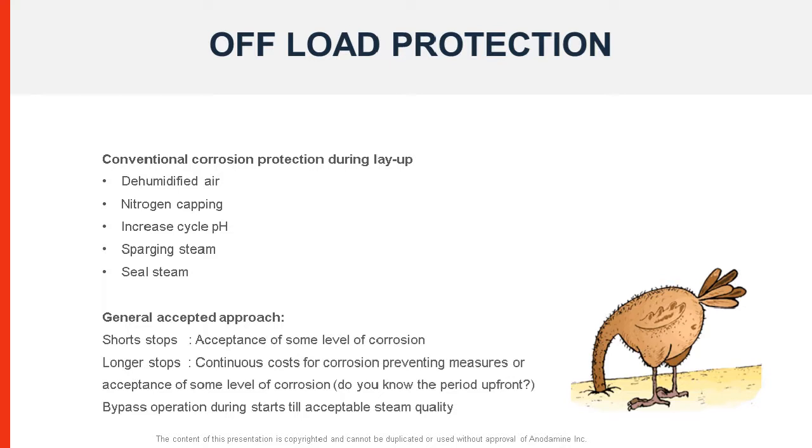Failure mechanisms will interfere with the plant's availability. It's that simple. The choice of cycle chemistry is strongly depending on the metallurgy and how the unit is operated. Extended offload periods leaving oxygenated stagnant water in any circuit is bad practice and will cause pitting and increased loads of oxide transport during starts. In most of the plants, operators increase the pH with extra ammonia before offload periods. The success of this layup method depends very much on whether the unit is put into service as planned within hours, some days, or the grid demands leave the unit longer and unplanned out of service.